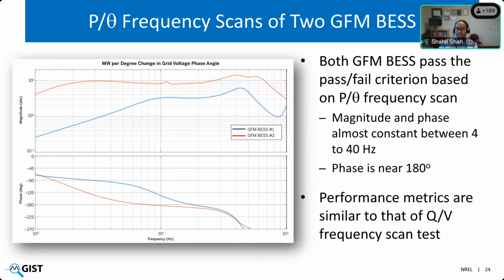P by theta scan has a similar performance matrix. Again, we are looking at basically the magnitude within 4 to 40 hertz, that the magnitude should be higher than a particular value, like 0.5 per unit per radian, and then the phase to be closer to 180 degrees, as in this case.